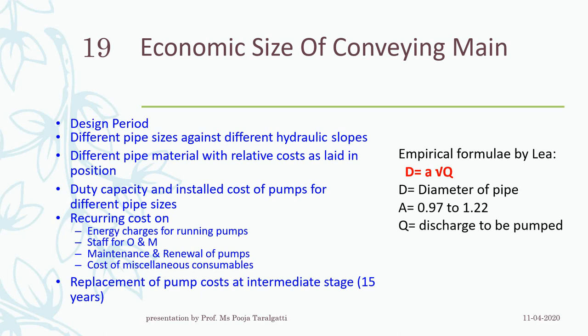Fifth: recurring costs related to operation and maintenance — energy charges for running the pumps, maintenance and renewal of pumps, and the cost of consumables. Also, the replacement of pump cost at intermediate stages: generally pumps are designed for 15 years while pipelines and other equipment are designed for 30 years. Because pumps work 24 hours with frequent open-and-shut cycles, their lifespan is reduced, so the design period for pumping systems is considered 15 years, while the pipeline design period is 30 years.